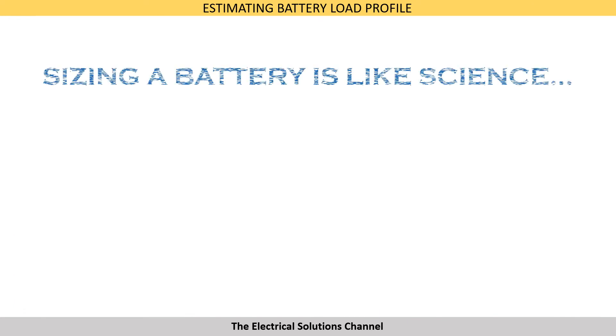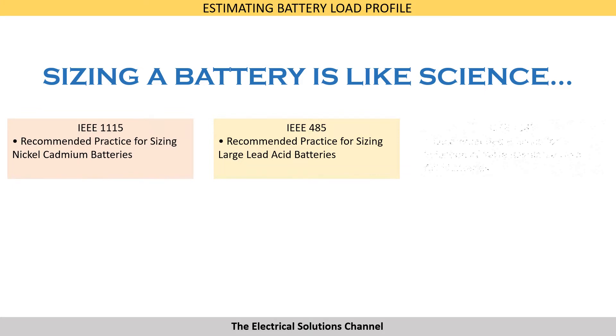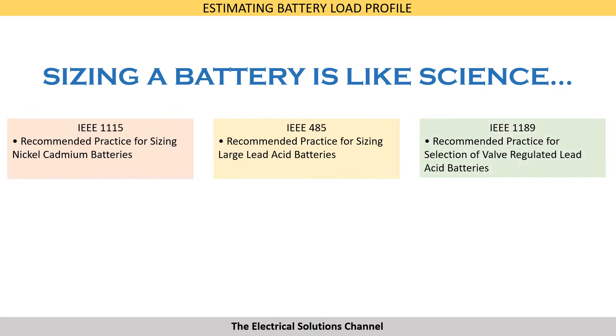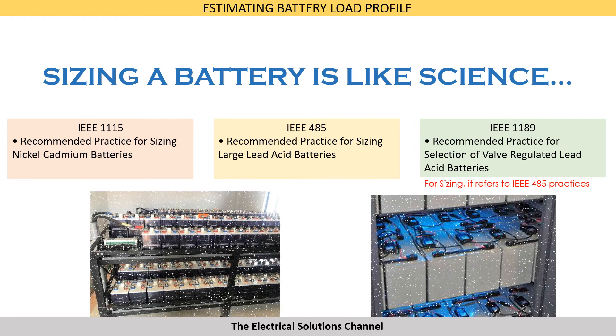Sizing a battery is a science, and there are various standards which dictate the exact steps to be followed. IEEE 1115 provides the recommended practice for sizing nickel cadmium batteries. IEEE 485 provides the recommended practice for sizing large lead acid batteries, whereas IEEE 1189 provides the recommended practice for selection of valve regulated lead acid batteries.